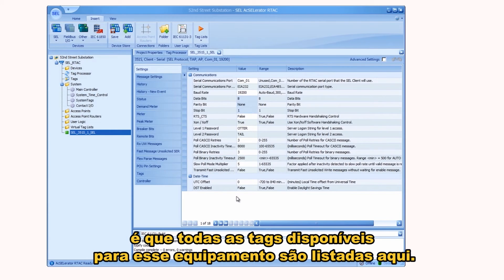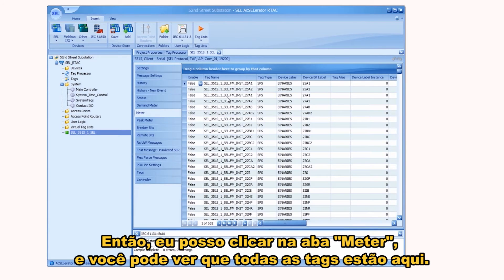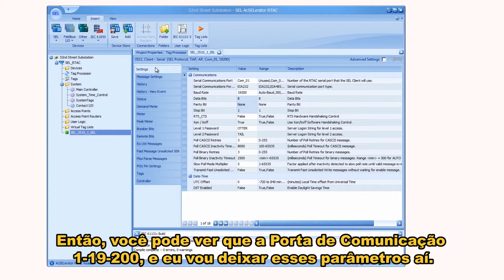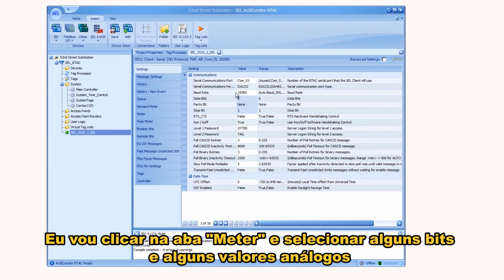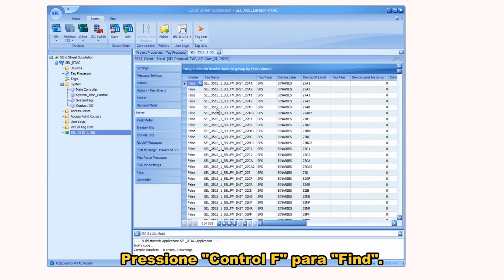The really cool thing about the SEL protocol on the R-TAC is that all of the tags that may be available for that device are listed here. I can click on the Meter tab and see all of the device tags listed. The Settings tab has the communication settings — you can see it's communication port 1 at 19200. I'm just going to leave those parameters there and click on the Meter tab.